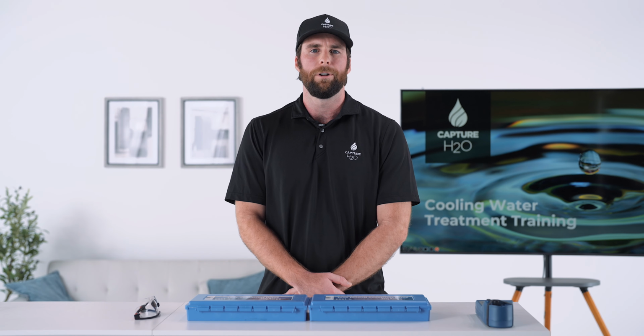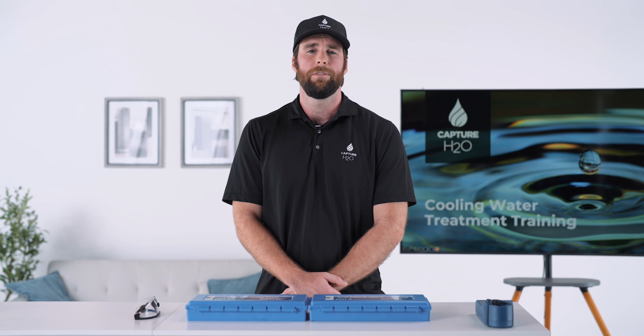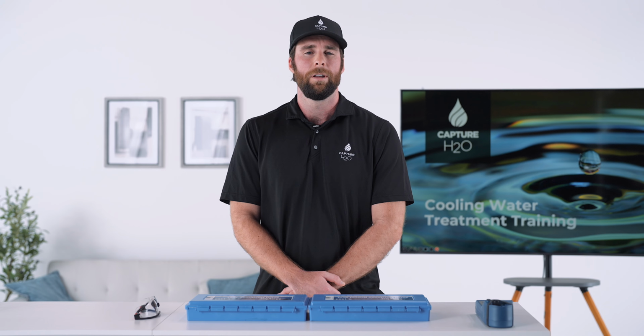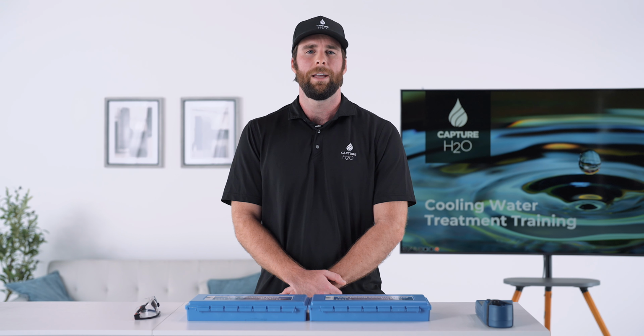If you're doing your operator logs and you find that the tower conductivity probes are out of calibration, you will need to recalibrate them. This is done by entering the controller, setup and run, selecting the system, selecting calibration, conductivity probe, and then you will punch in the conductivity that is on your Myron handheld meter.